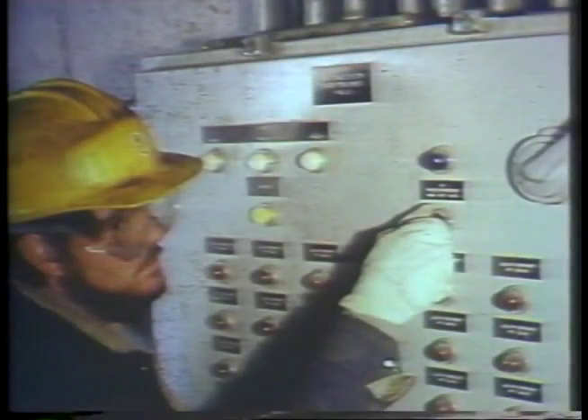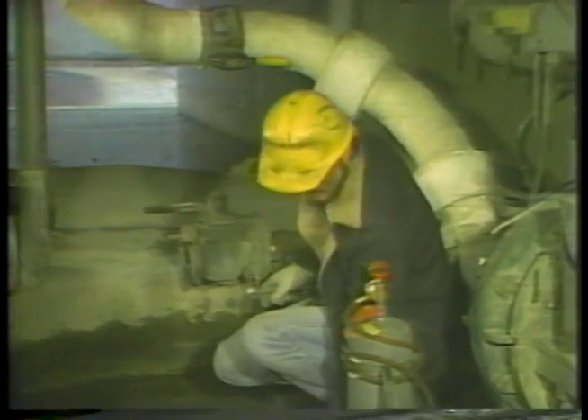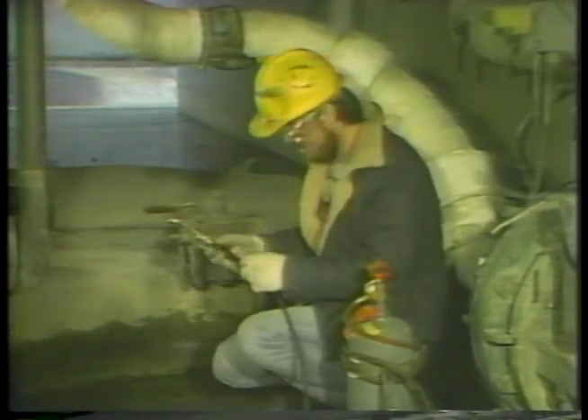Re-establishing heat tracing will thaw the line. But you may not be able to put the heat tracing back into service. If the line must be operated, you may have to thaw the pipe using a torch. Only use a torch in an area where an open flame is permitted, and always follow established plant procedures.